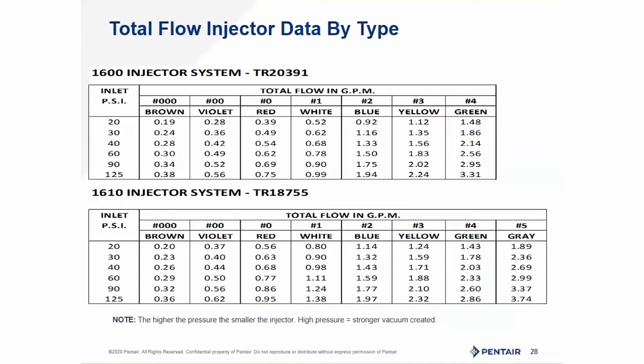That also explains why we can't have any obstruction or scale buildup or defect in that nozzle tip. If you nick or scar that nozzle tip, you'll change the flow path, and you'll mess up the Venturi action, and you won't create a draw. That's why it's critical to get those in the proper order and the proper flow path.